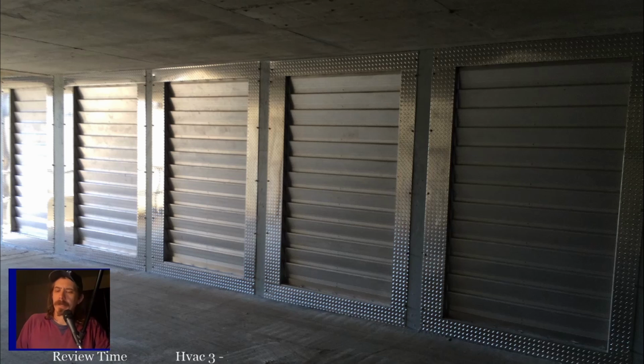Sorry about that. But anyway, I know I mentioned before that when you've got something that trips on high pressure, you got an RTU, especially as it's getting old, and it tends to trip out on high pressure. Or even if it's not that old, if it's had some issues before where condenser motors are failing or something, you'll see situations where those high pressure switches just open and close a little too fast, and it ends up short cycling the compressor. So if you've got some kind of lockout relay in there, then you can stop that short cycle by making it lock out, so it has to be manually reset by cycling power.